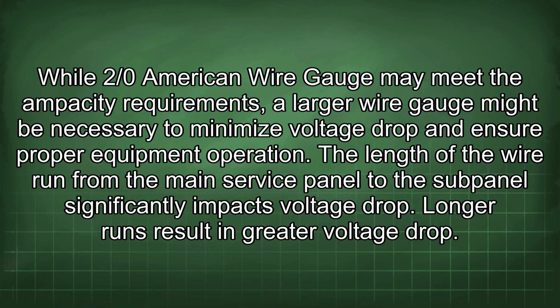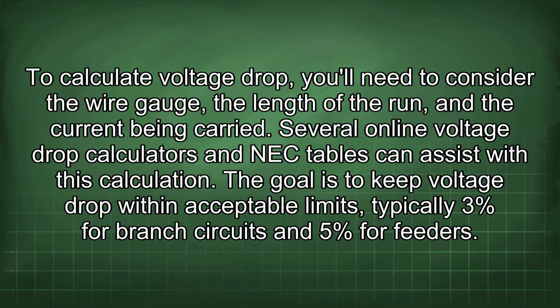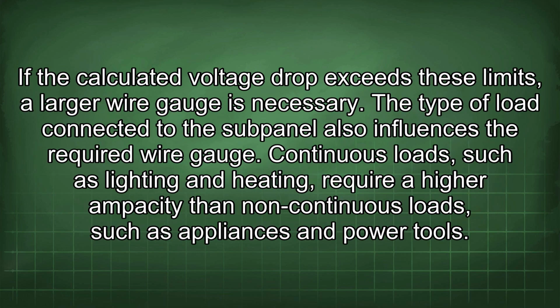The length of the wire run from the main service panel to the subpanel significantly impacts voltage drop. Longer runs result in greater voltage drop. To calculate voltage drop, you'll need to consider the wire gauge, the length of the run, and the current being carried. Several online voltage drop calculators and NEC tables can assist with this calculation. The goal is to keep voltage drop within acceptable limits, typically 3% for branch circuits and 5% for feeders. If the calculated voltage drop exceeds these limits, a larger wire gauge is necessary.